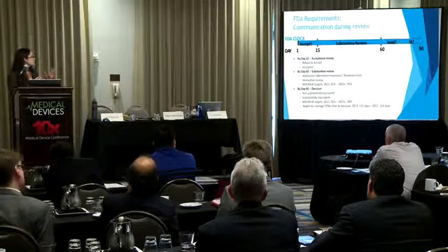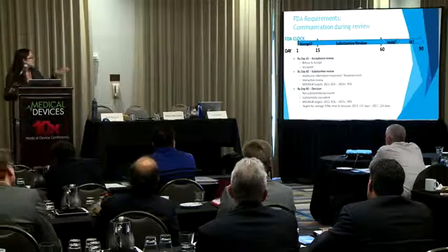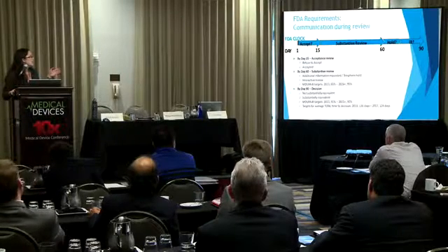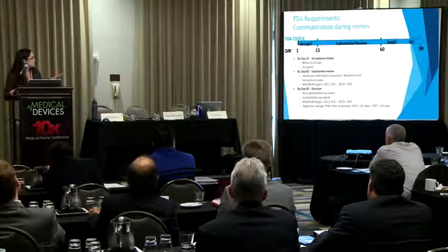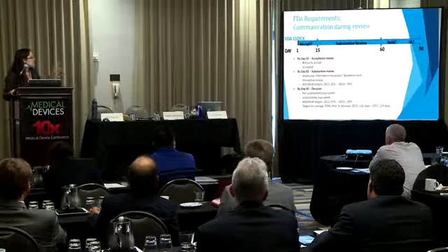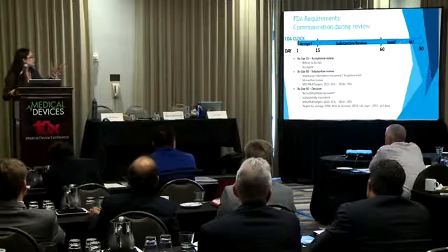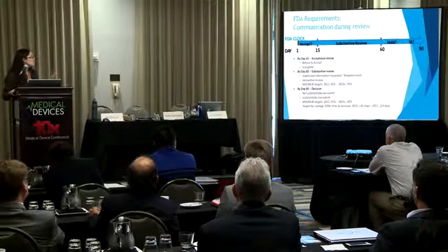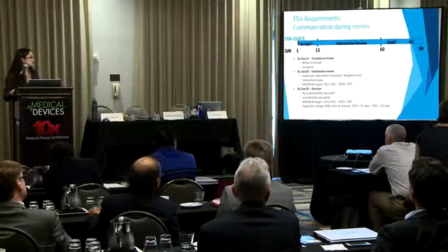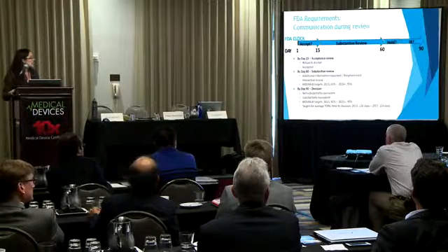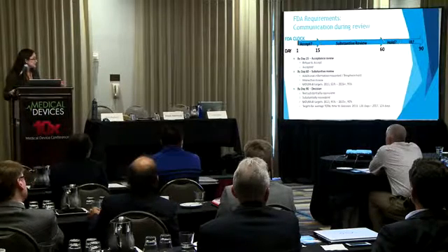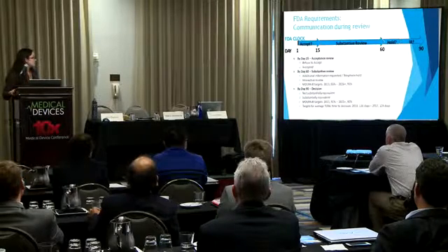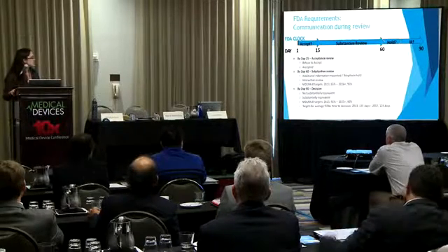So the MDUFA targets, I'm not going to explain MDUFA, but the goals that FDA had, by 2013, they wanted 65% of the submissions to have a substantive review or an interaction by day 60. By 2016, they're wanting 95% of these. So you'll see the reviewers are going to really try and stick to this day 60. By day 90, you get a decision. So it's either not substantially equivalent, an NSE, or it's substantially equivalent, which is SE. So there are the targets again for the decision date.